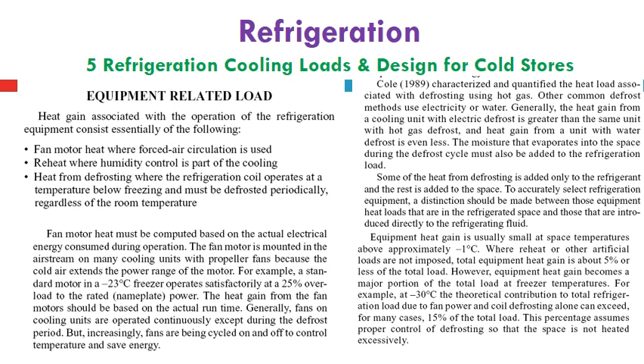To accurately select refrigeration equipment, a distinction should be made between those equipment heat loads that are in the refrigerated space and those that are introduced directly to the refrigerating fluid. Equipment heat gain is usually small at space temperatures above approximately -1 degree Celsius. Where reheat or other artificial loads are not imposed, total equipment heat gain is about 5% or less of the total load. It should not exceed 5% of the total load of the first four segments of the load.